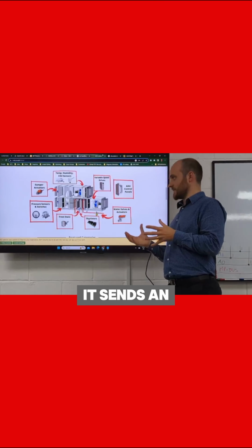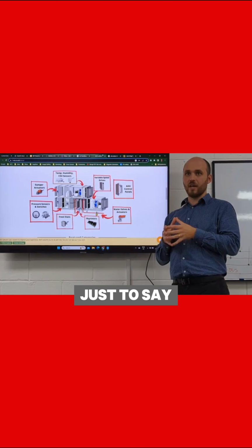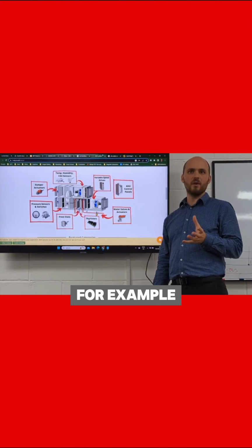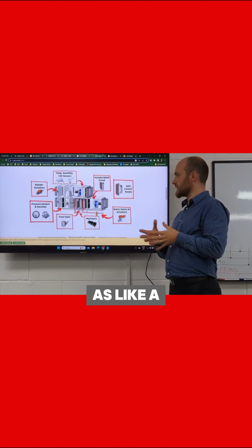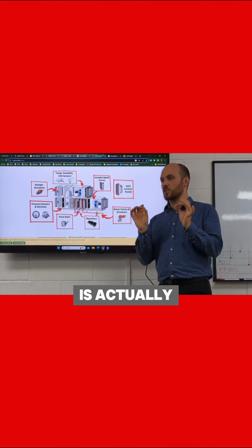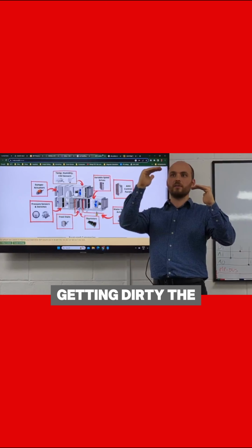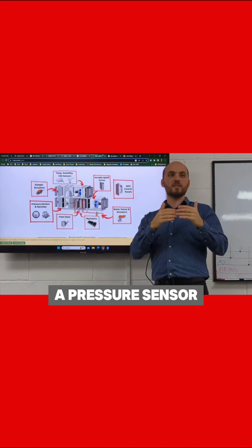What it does is sends an input signal to our controller just to say your filter's dirty, for example. It doesn't have the same knowledge as a sensor. A pressure sensor is actually measuring the exact pressure reading at every stage of the filter getting dirty. The benefit of that is a pressure sensor can give you multiple signals back to the controls, not just one.